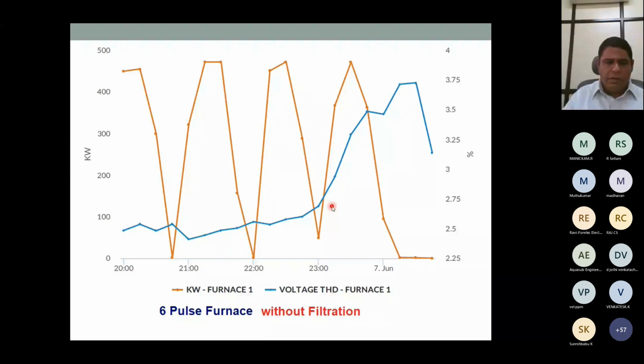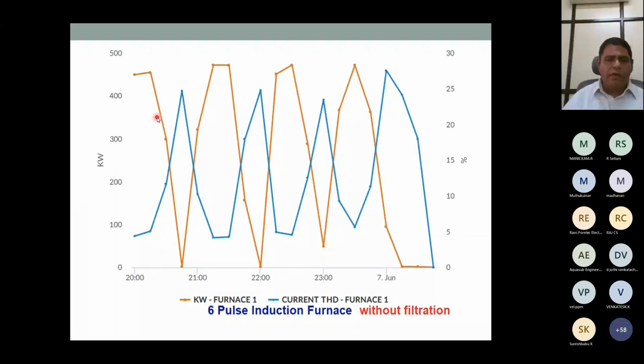But in case of current, it will be different. This is in case of current, where when the load drops down, the harmonic goes up. Again, this is an instantaneous value. It is not a continuous spectrum. It is an instantaneous value, and this should not be considered. Just for understanding purposes, I have told that the brown is the kilowatt of the furnace and the blue is the harmonic content. So when the load is more, the harmonic content was less. When the load drops down, the harmonic content goes up.